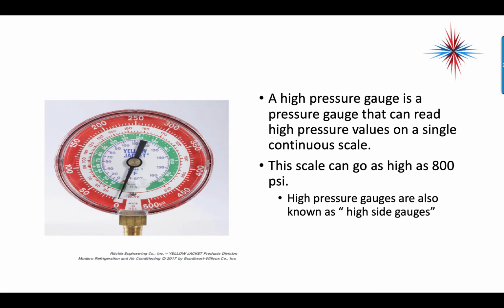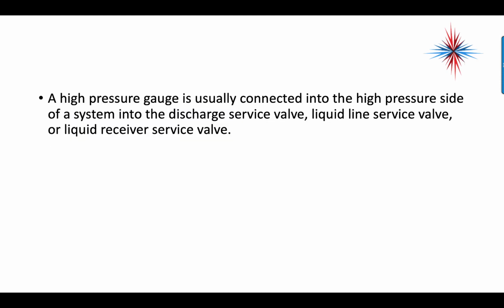A high pressure gauge is a pressure gauge that can read high pressure values on a single continuous scale. This scale can go as high as 800 psi. High pressure gauges are also known as high side gauges. The high pressure gauge is usually connected into the high pressure side of a system into the discharge service valve, liquid line service valve, or liquid receiver service valve.